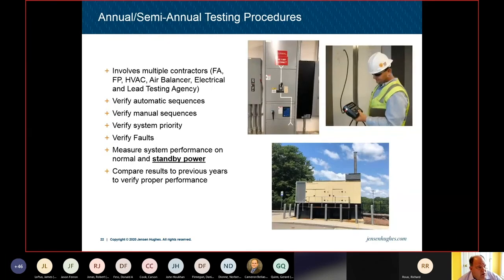So what are some of these annual and semi-annual testing procedures? Well, you have to involve a whole lot of people. We're talking about the fire alarm contractors, the sprinkler contractors, HVAC people, the air balancer, and an electrician or someone from the building that's comfortable with dumping building power, in addition to a lead testing agency. That lead testing agency is really acting like the smoke control special inspector for this semi-annual test. So you really want an experienced fire protection engineer that knows the ins and outs of smoke control and can tie the bits and pieces together, to thread all of those integrated systems together to work as one.